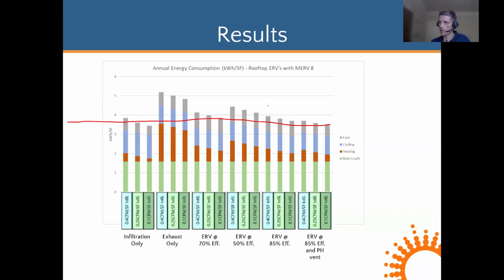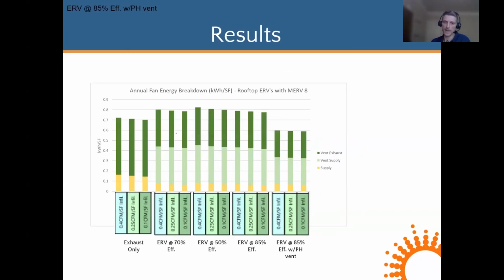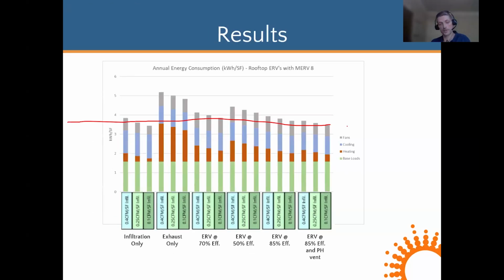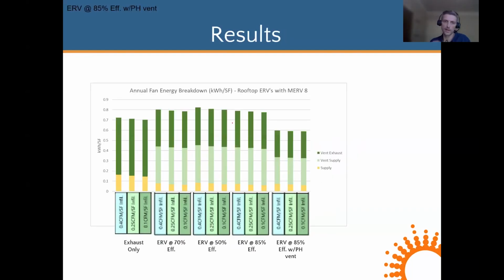Looking at just the fan power of rooftop ERVs, now we see that with that increased static pressure in a rooftop ERV unit, there is definitely an increase in fan energy. And now the fan energy for the ERV units is greater than the exhaust only scenario. However, the total consumption is still much lower in the building. And then as we increase effectiveness, we see increased savings to be expected, and the passive house level flow rates again widens the gap in savings and reduces the ERV fan power to lower than the exhaust only scenario.